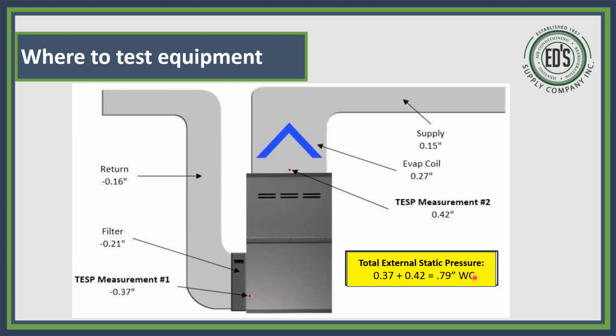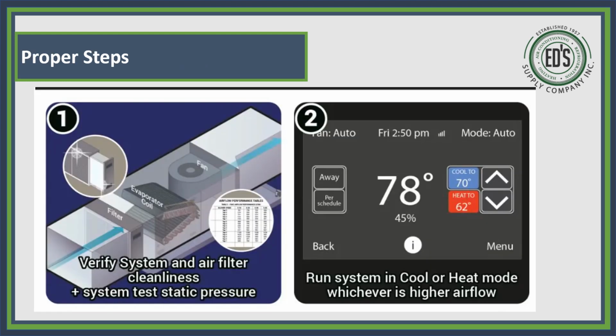And then we'll show you, so if I'm looking at this number here, I know I'm a little high here on my supply, but I'm really high right here. So if I could get this 0.37 down to 0.16 just by removing this filter, I'm going to be up here at the 0.16, and then you add 0.16 to the 0.42, and you see you got 0.58 or 0.6. So you see how much I gained just by taking that filter out. So then let's go with the proper steps of how to actually check it.